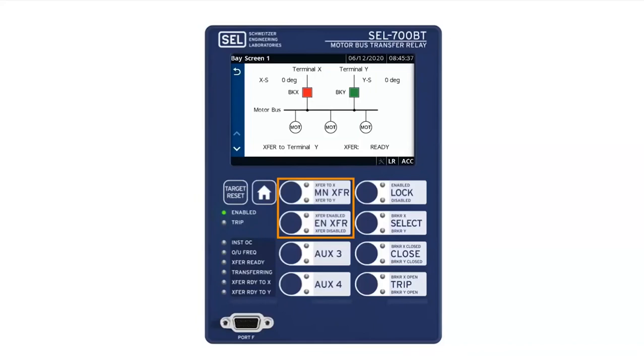Another question: with the 700BT being a new product, how did SEL test and validate the fast in-phase capabilities? We have an engineering services division, and they do bus transfer applications. So we have lots of recordings from the field that we use to design and to test the relay. We also do quite a bit of RTDS testing in R&D. Engineering services also does its own modeling for bus transfer, so we tested that too. We have spin down recordings from several motor models, and we also have a demo unit with the motor models and the main-tie-main application with all the auxiliary contacts and 52As, and we applied it and compared it to other fast transfer relays and solutions.